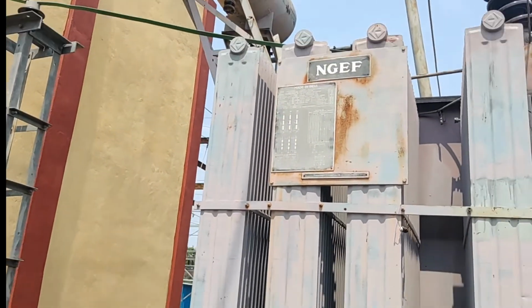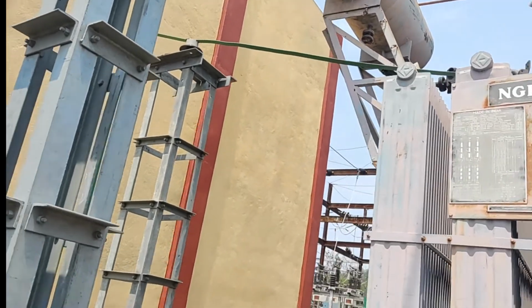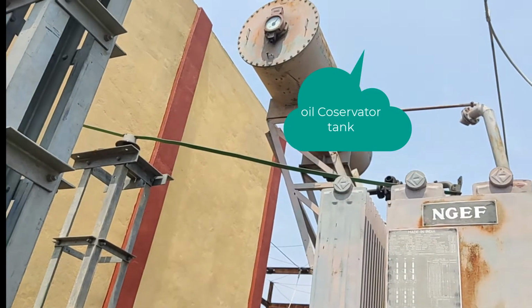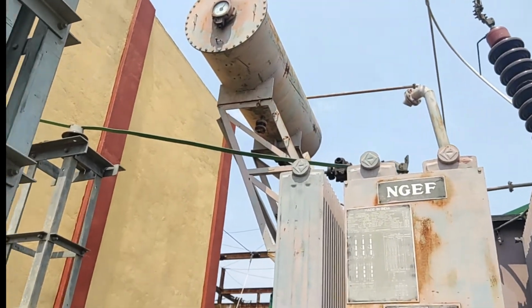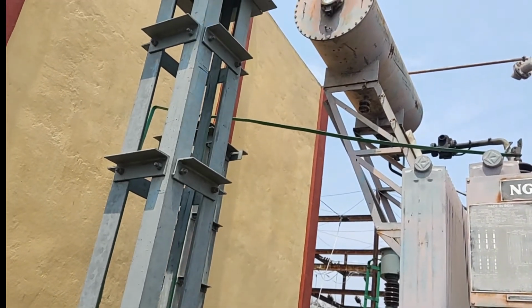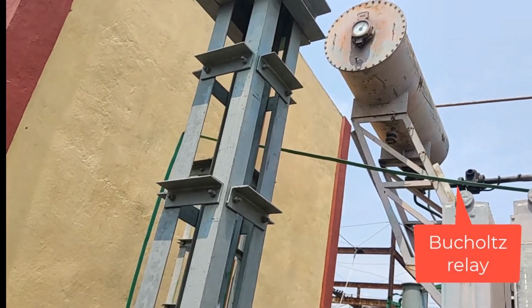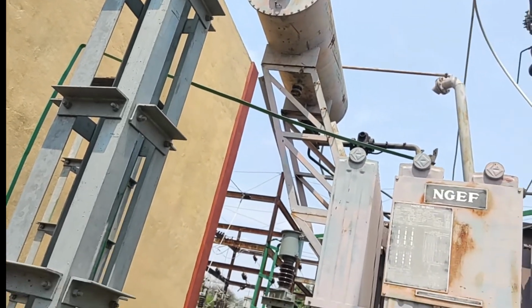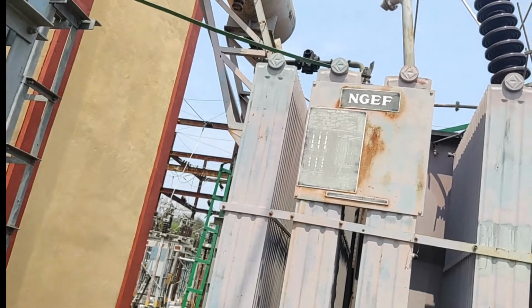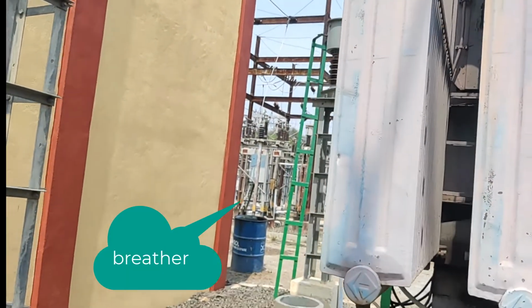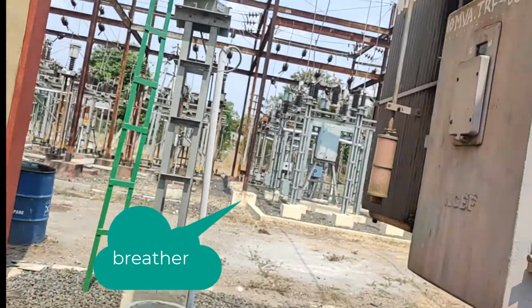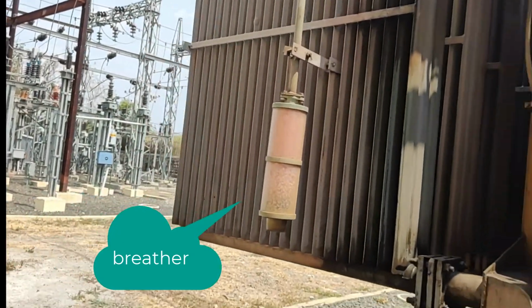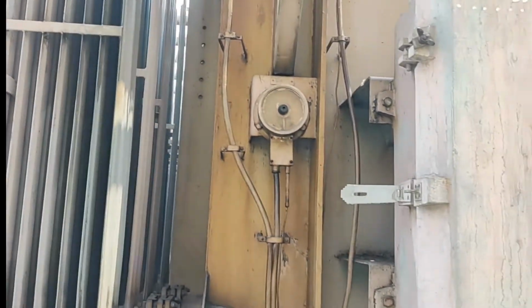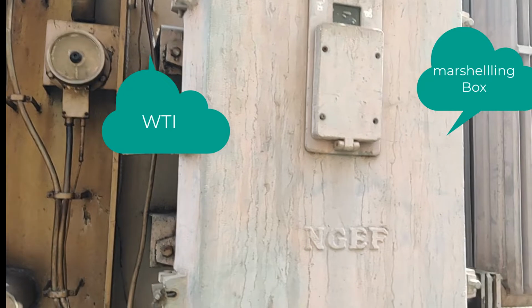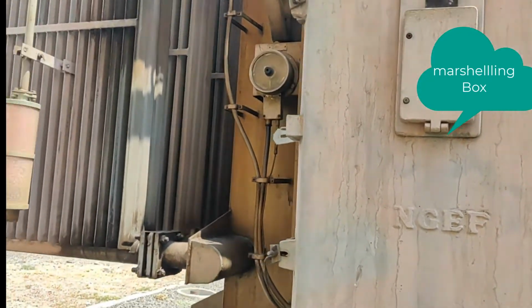This is the conservator tank of the power transformer. In the next video I will explain in detail what the conservator is, what its different parts are, and its working. You can also see the Buchholz relay there, and you can find the NCT. You will find here a marshalling box and OLTC, and this is called the breather. There is a temperature indicator over there which indicates the winding temperature, and one more indicator will indicate the temperature of the oil.